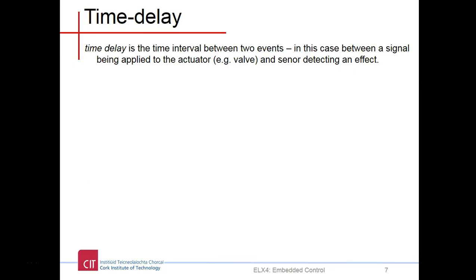There's often another parameter we see when we capture real data called time delay. This is the interval between two events: a signal being applied to the system and the sensor detecting it. For the tanks, it's turning on the pump and the level beginning to change. For the heaters, it's turning on the heater and the thermistor picking up a change in temperature.